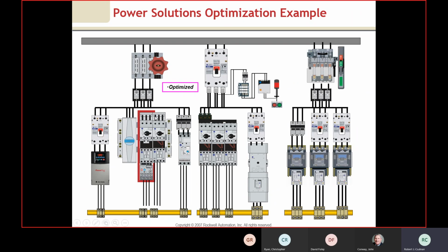In this example, just because there was a lack of space, you probably wouldn't use the bus bar system for two starters. Remember, I said 3 or 4 is when it starts to optimize itself. But this just gives you an example of that. It's something that can be included in a system or setup where there may be separate starters or separate connections not tied into the bus bar system.